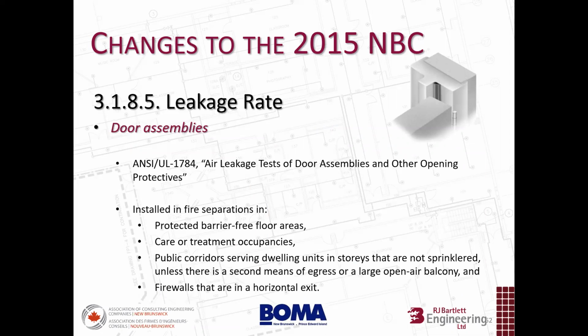Okay, so there's a standard here that's referenced with respect to leakage rate: air leakage tests of door assemblies and other opening protectives. The leakage rate applies to doors that are installed within fire separations in protected barrier-free floor areas, care treatment occupancies, and public corridors serving dwelling units in stories that are not sprinklered, unless there's a second means of egress or a large open air balcony. So in a smaller building, if occupants are able to find refuge on their balcony, then the door leakage rating is not required. And in buildings where we have horizontal exits through firewalls, those are also required to have this new leakage rating.